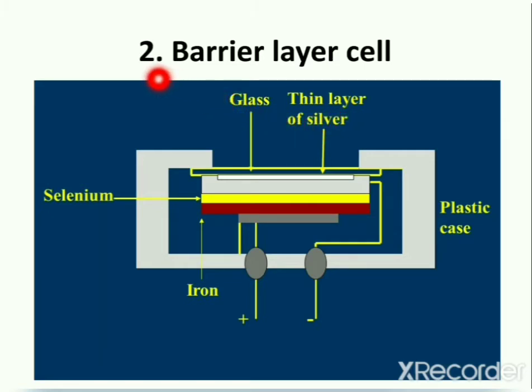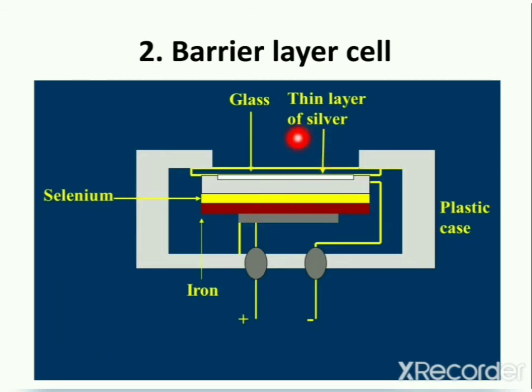When radiation coming from the sample falls upon this thin layer of silver or gold, it generates electrons. The electrons are attracted towards the iron surface because it is maintained at positive potential, but the selenium semiconductor stops the transport of electrons towards the iron surface. This causes accumulation of electrons on the thin layer of silver, producing a voltage difference between the silver surface and the base of the cell. A photocurrent flows which is directly proportional to the intensity of the incident radiation beam. Barrier layer cells are also very sensitive in nature.